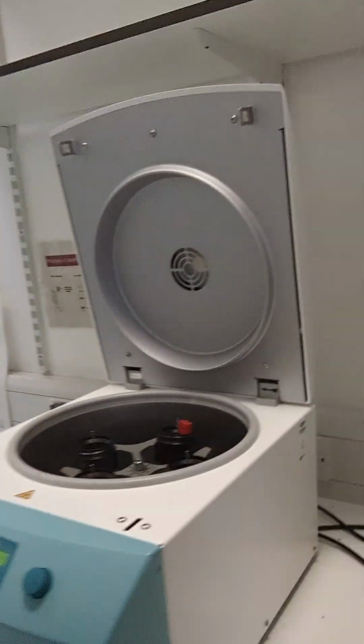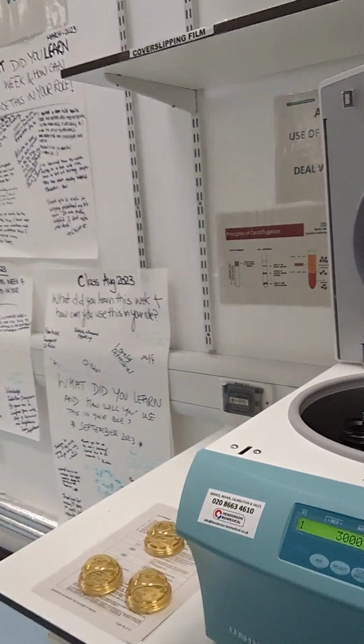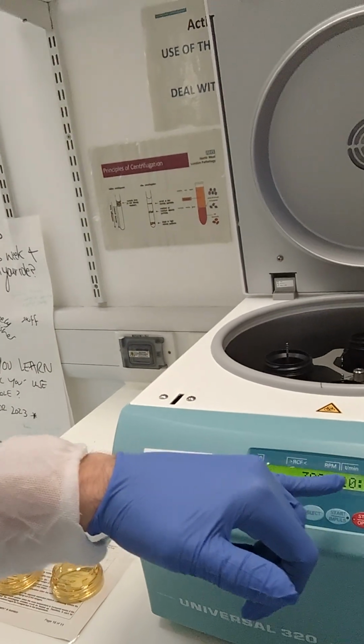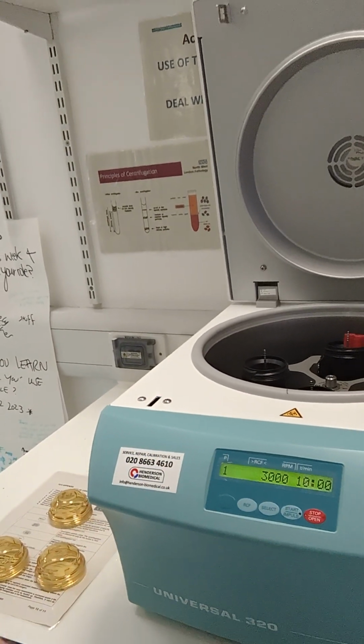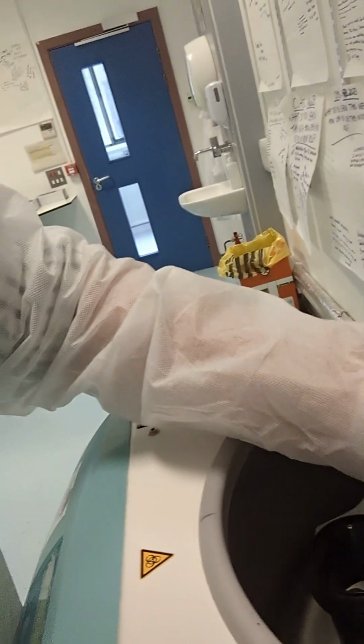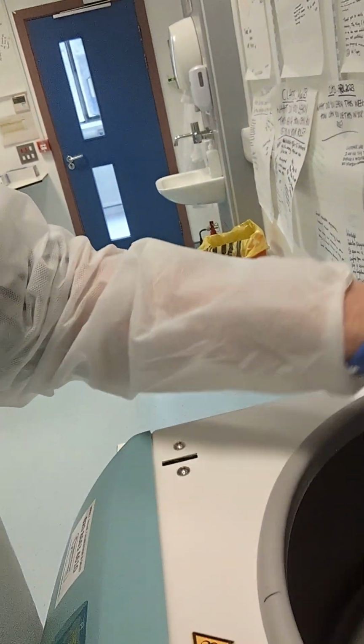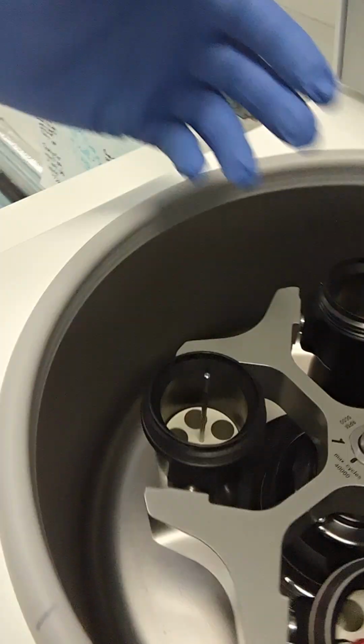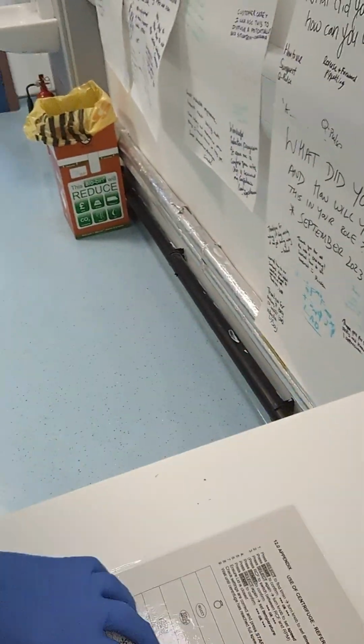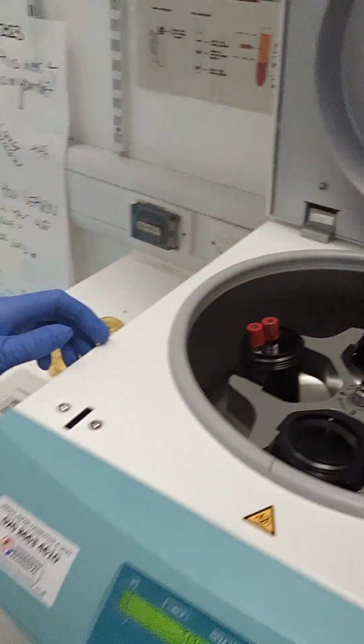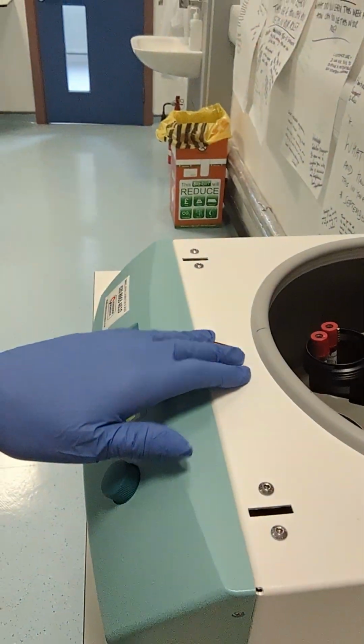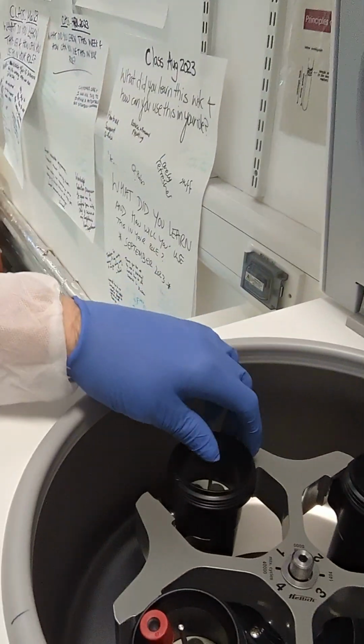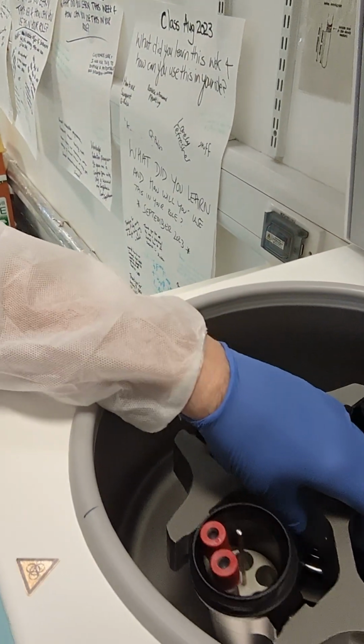Firstly, make sure there's power and that the centrifuge is switched on. Make sure the settings are correct, that it's set at 3000 RPM and the spin cycle is for 10 minutes. Check all the components are there so that you've got your adapters, the buckets rotate, there's no debris in the rotor, and that you have your 4 BioSeal lids. Just check for wear and tear, that there's no damage to the seal, the lid is working, and that the rotor, that there's no cracks or signs of wear.